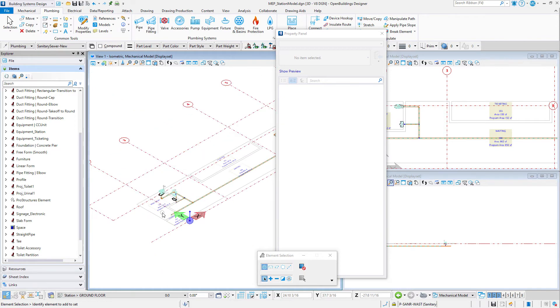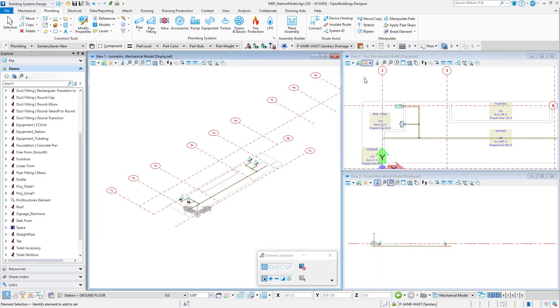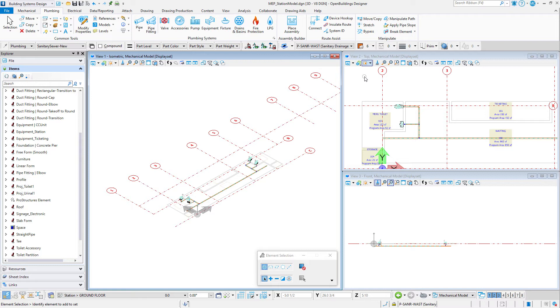Close the Place Component dialog. Now that the plumbing route has been placed, you will use the Apply Slope tool to properly slope the pipes. Apply Slope is a manipulation tool that is used to apply a slope to an existing route by sensing downstream connected components. The slope can be applied either up or down from a selection or start point and will continue through connections and even vertical risers if this option is selected. However, the slope will continue in the same direction, so the start point must be selected carefully.